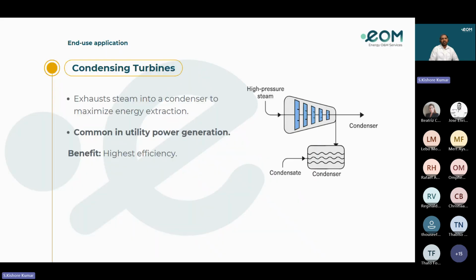Condensing turbines. A condensing turbine is a type of steam turbine used primarily in power generation, where the steam expands to below atmospheric pressure in the last stage and is then condensed into water in a condenser. Exhaust steam goes into a condenser to maximize the energy extraction. It is commonly used in utility power generation. The benefit is that it has the highest efficiency.